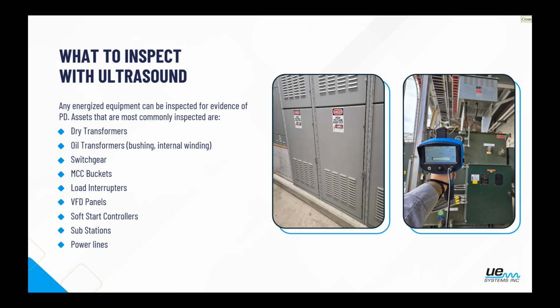We also typically look at switchgear, MCC buckets inside that room, load interrupters, VFD panels, soft start controllers. As you saw previously, substations are an easy one to inspect, as well as outdoor power lines. Typically, they're medium and high voltage that we would be inspecting. And once again, a lot of that, we're looking specifically for corona, but we can still inspect for tracking and arcing as well.